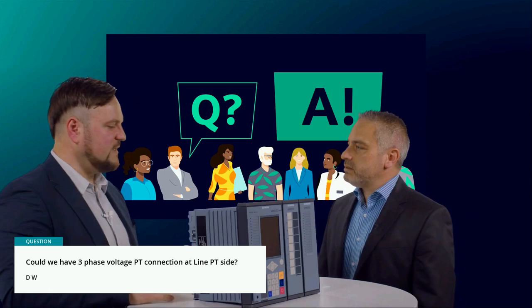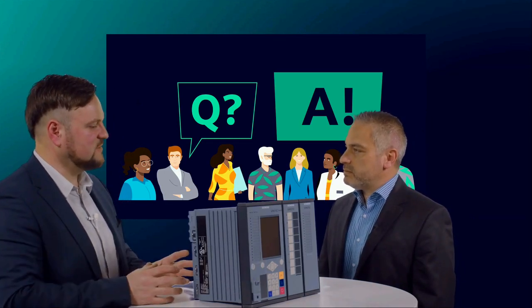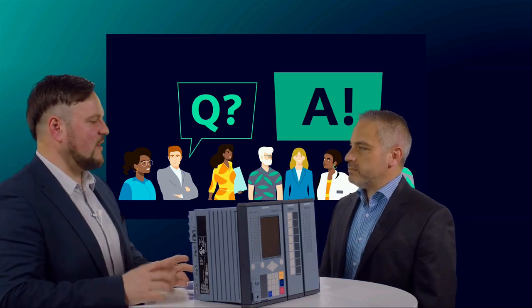Could we have three-phase voltage PT connection at the line PT side? Yes, you can. Basically, the three-phase voltage connection is recommended, and on most new applications we will have three-phase CT sets and VT sets. Especially for retrofit applications, we will find phase-to-phase voltages, single phase. This is currently possible for the line side, not for the motor bus. But in the next release, we will also release a version especially for retrofit applications where we have only one VT set on the motor bus. This will come with the next version, I think with the 9.60 or 9.70.